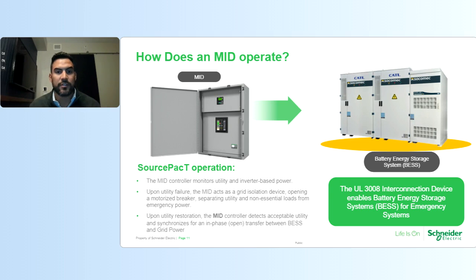So the way SourcePack communicates is through a C-form contact signal. It's a relay, and we're basically vendor agnostic. So any energy storage system or energy management system that can accept the C-form contact relay, we can communicate with them. Very similar to the way our transfer switches are designed, compatible with mostly any generator. Same concept here for the microgrid interconnection device.